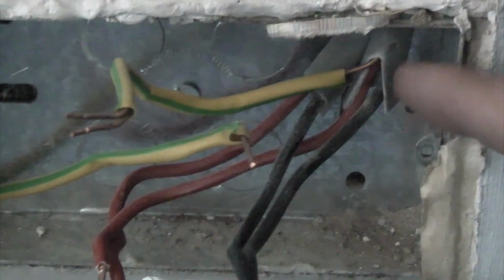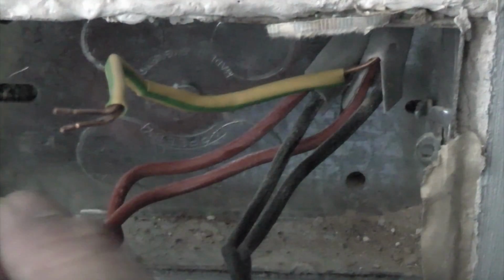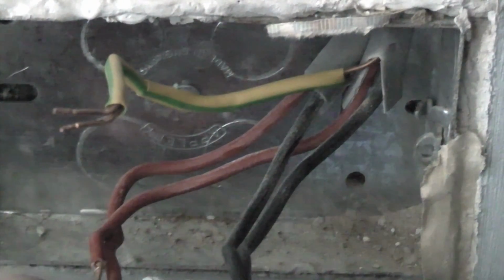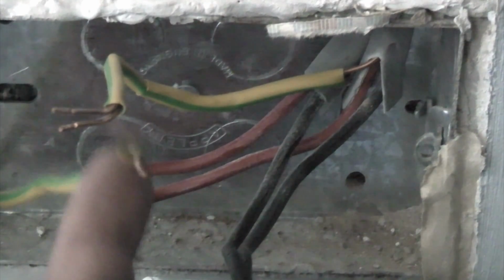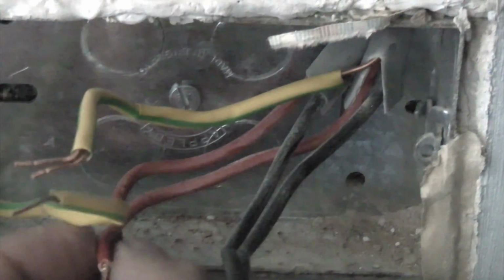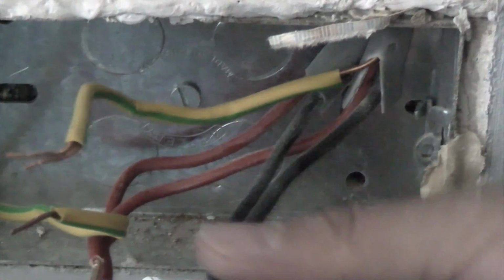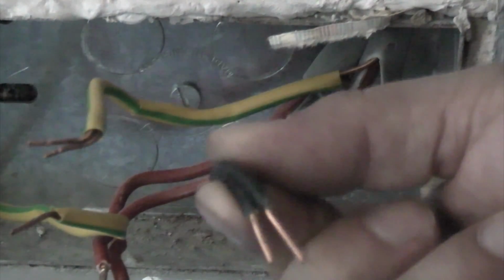And also, if you look here, you'll see that we've got 2 earth wires in there, which are coming from the circuit cables, and also an earth wire at the back there, which is supplementary bonding. So all those 3 will go into the earthing terminal. Those 2 will go into the live terminal, and those 2 will go into the neutral terminal.